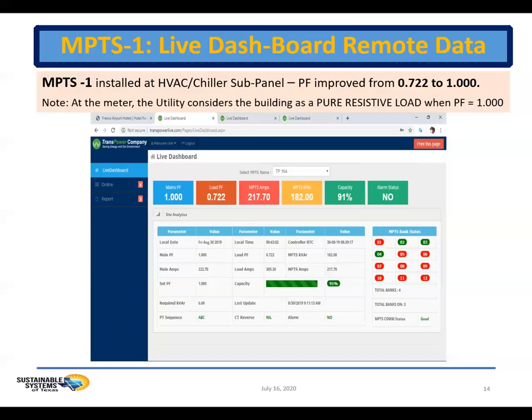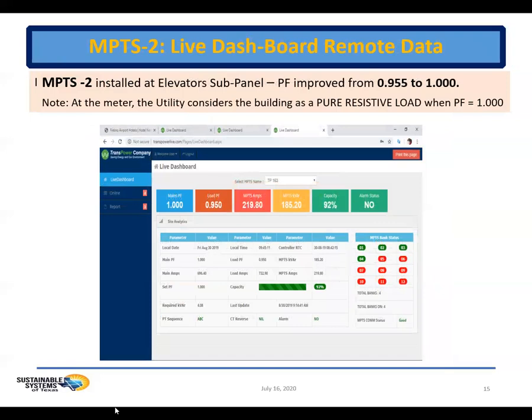So now let's look at MPTS dashboard number 2. Here we see the snapshot of this dashboard, and it's at the elevator subpanel, recording a load power factor at 0.95. All 4 banks on the system are operating in OK. The main power factor of the subpanel is improved to 1.0, and the MPTS is at 92% capacity. Notice that the amps decreased from 732.9 with the MPTS off to 696.4 with the MPTS on. That's a 4.9% improvement in amps.